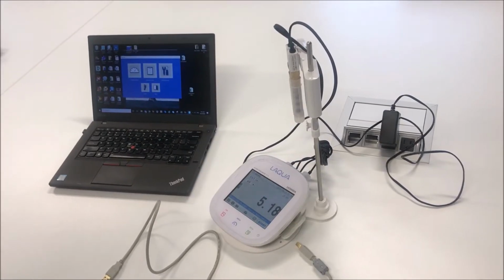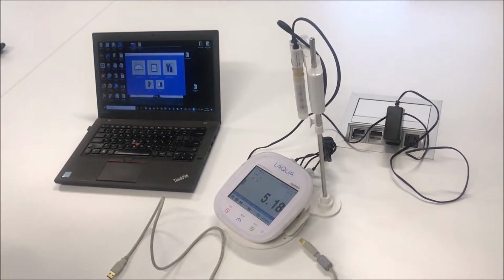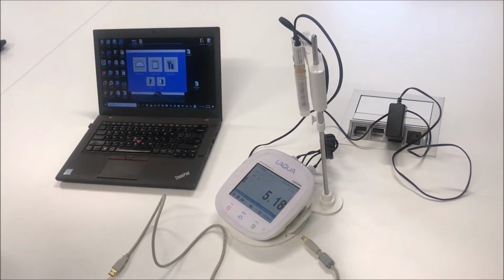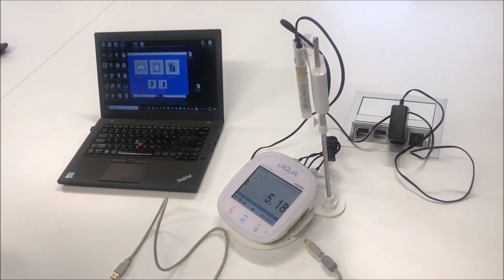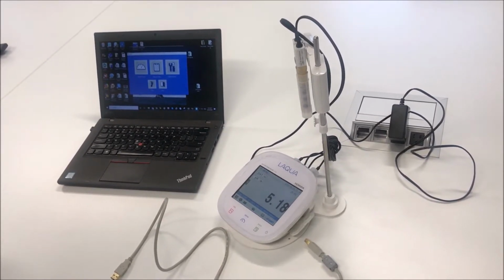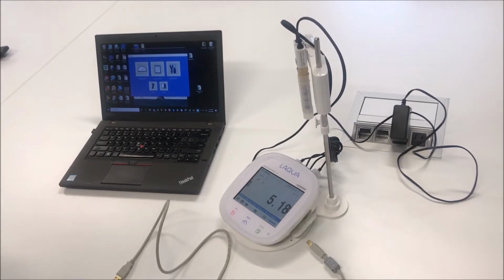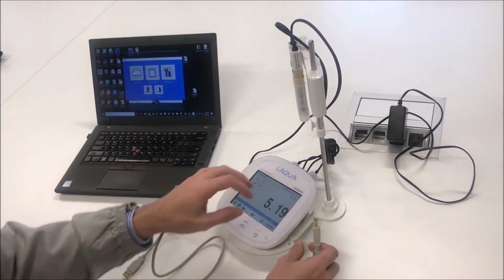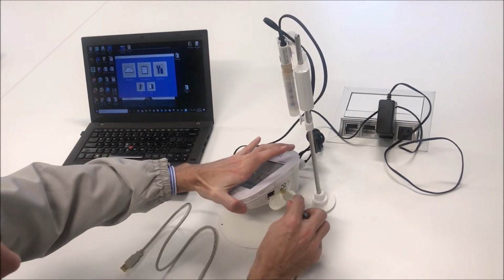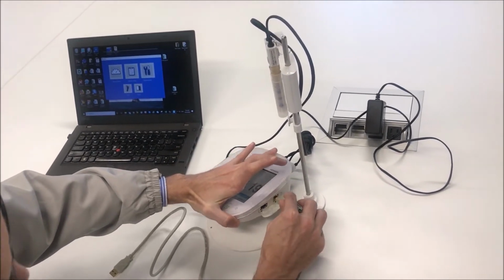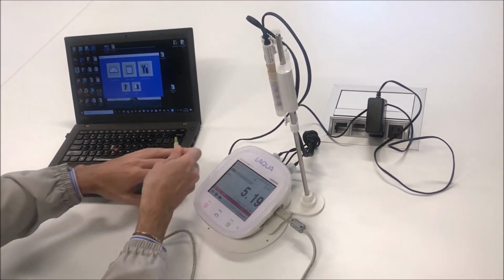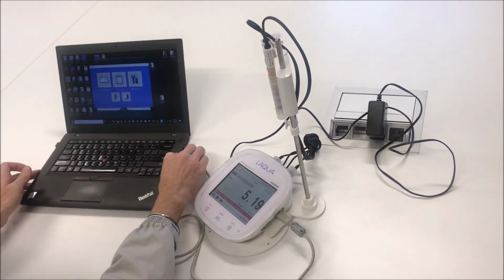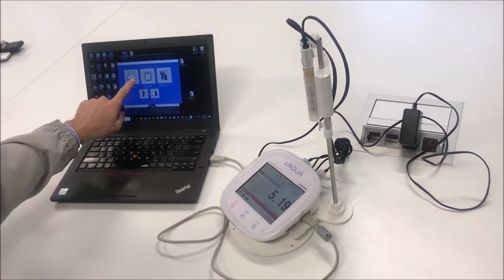Hello, today I would like to explain how to use the HORIBA LAQUA data acquisition software with the HORIBA benchtop pH meter. Today we will use the USB connection cable to connect the meter to the computer. We have here downloaded the software.